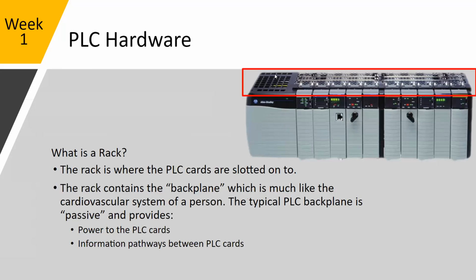So I was touching on this earlier, but what is a rack? The rack is where the PLC cards are slotted into. The rack contains a backplane, which is much like the cardiovascular system of a person. The typical PLC backplane is passive and provides power to the cards and information pathways to the processor. So like I was saying earlier, the processors will get information from these different cards, whether it's the communications card, whether this is going out to a drive, this one's going out to additional racks, or you have IO coming into them. All that information is passed through the backplane to the processor. The processors can talk back and forth as well. A configuration like this, I'm assuming, is redundant in some way. That's the only time I've ever seen two processors in the same rack.